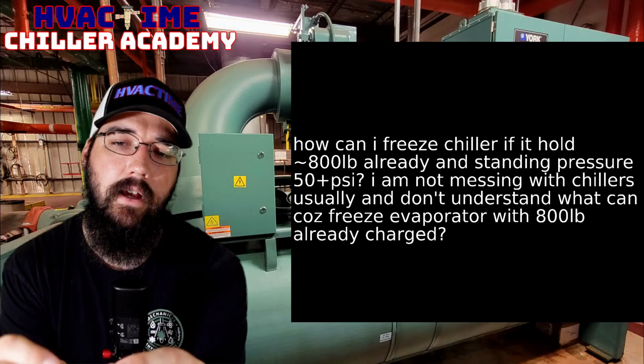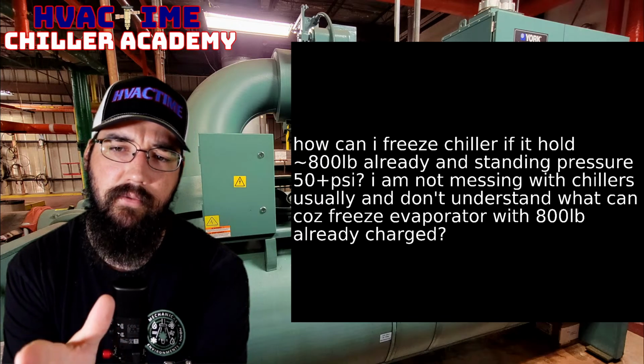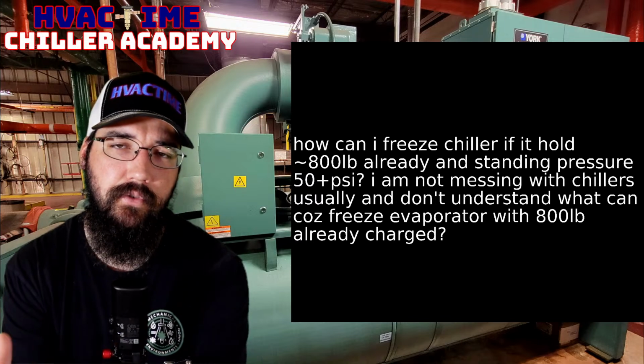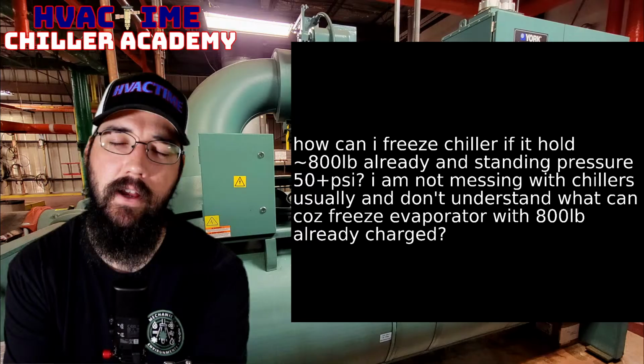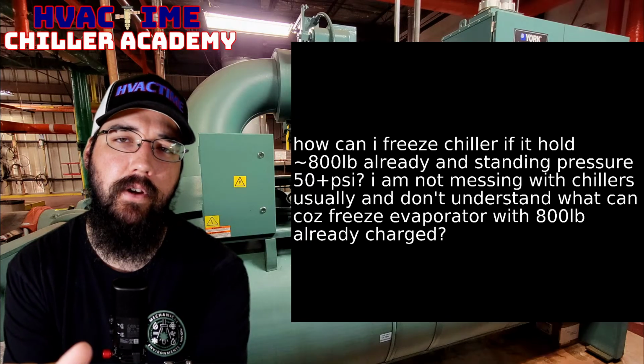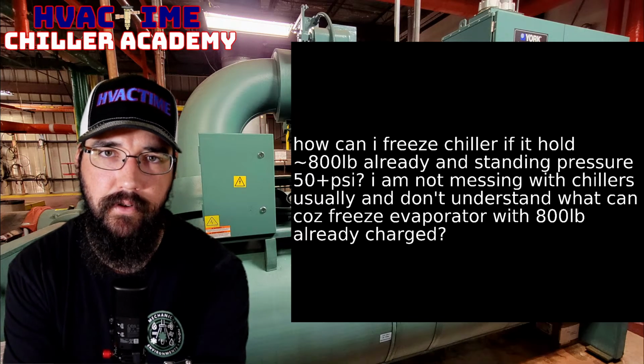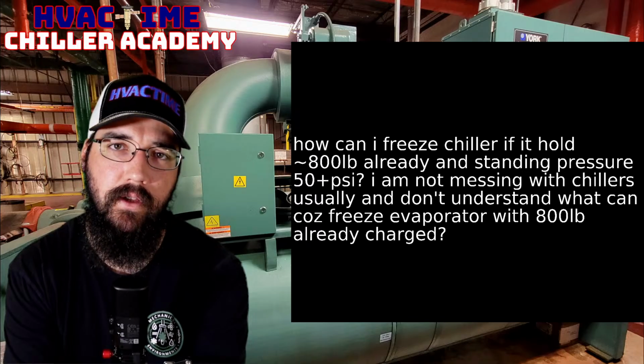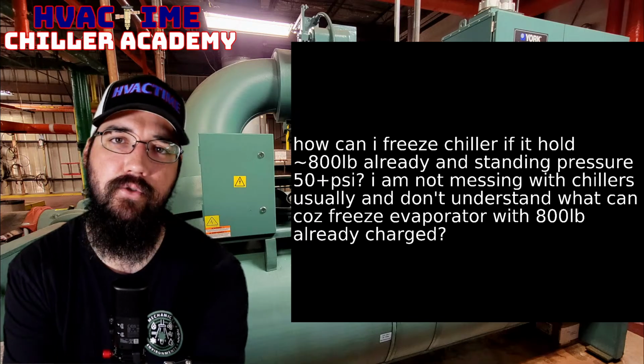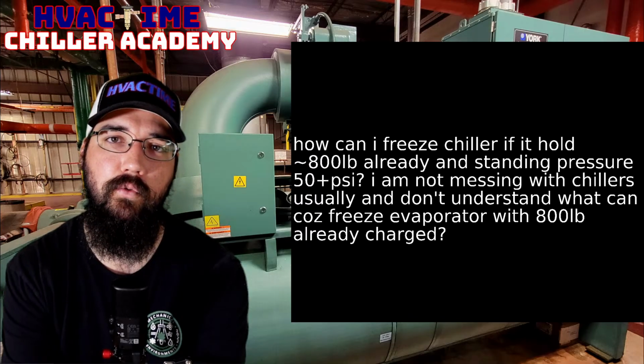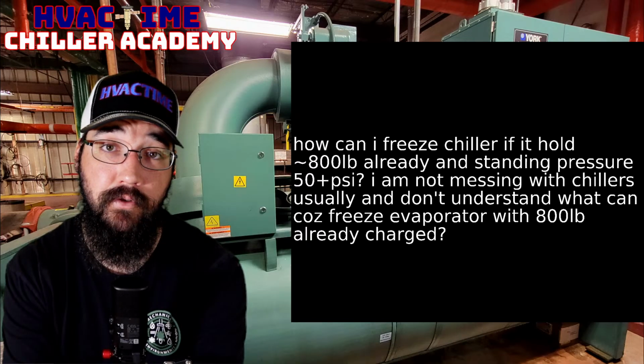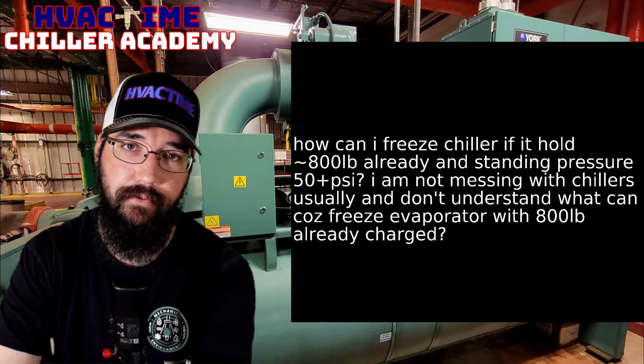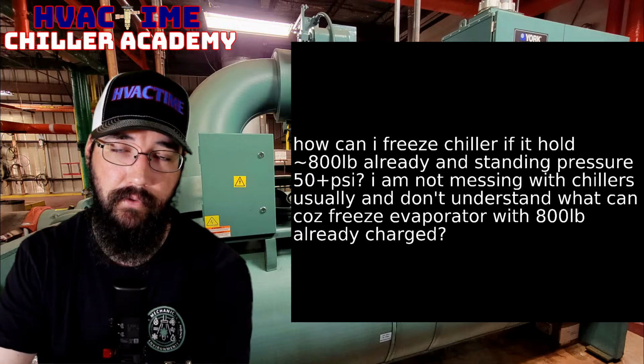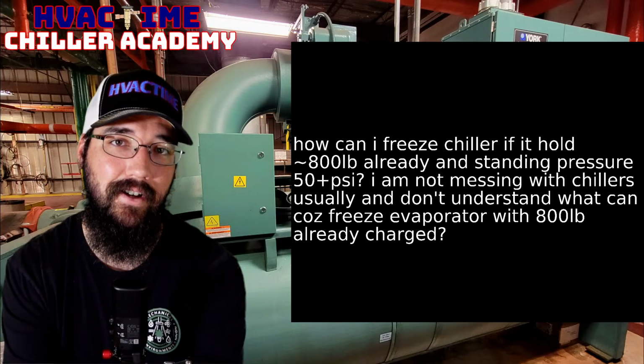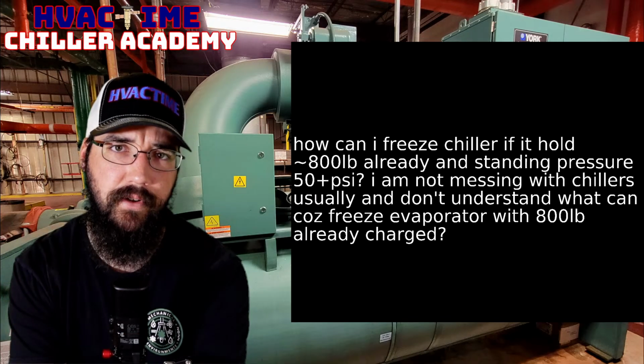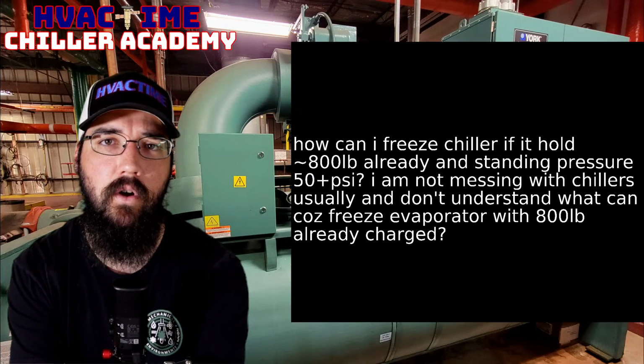Either way, if your standing pressure is above your freezing saturation point, you're fine. The point is, if your saturation is below freezing, then when liquid refrigerant makes contact with the tubes that have water in them, it can draw enough heat out of the tubes to freeze the water if we're below freezing temperatures. Now, if our saturation is above freezing temperature, once that liquid refrigerant contacts the tube, we won't drop below freezing to begin with.